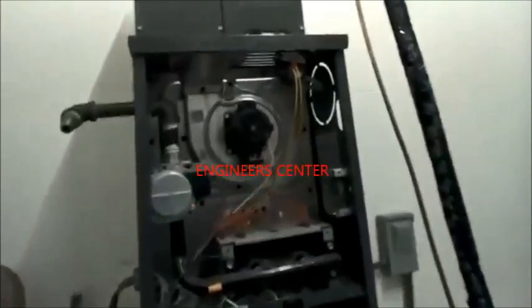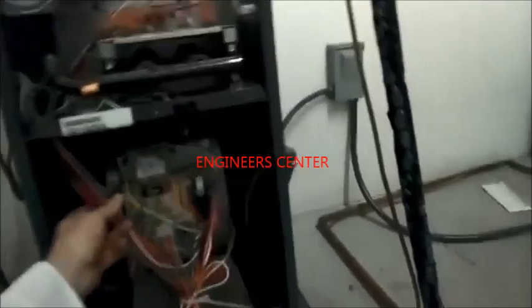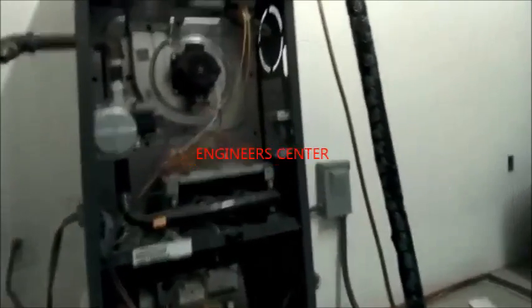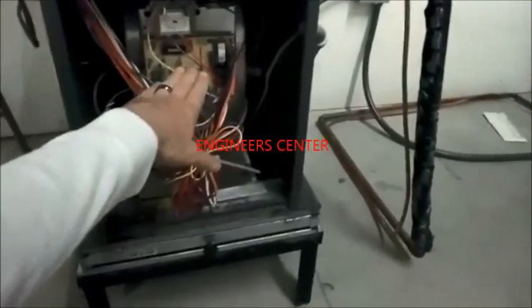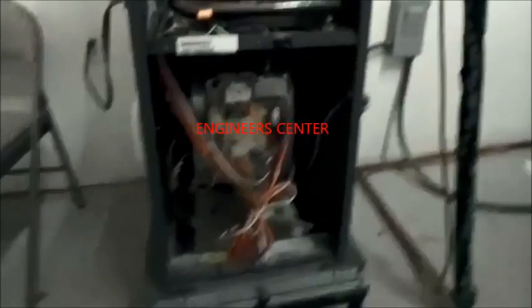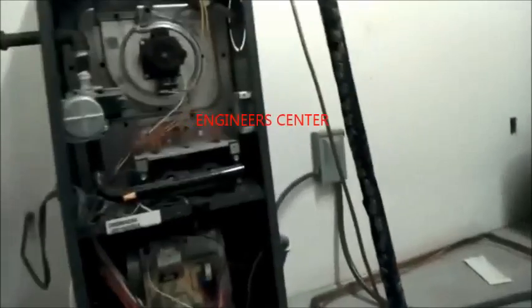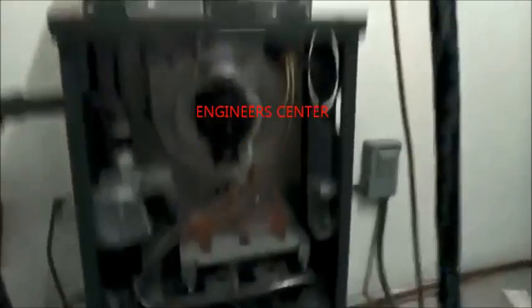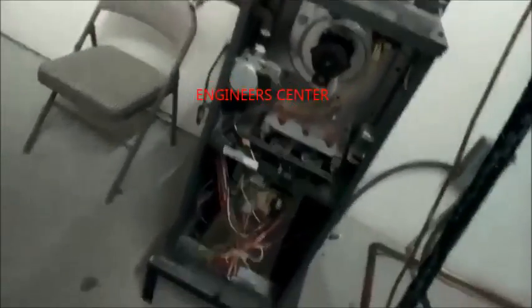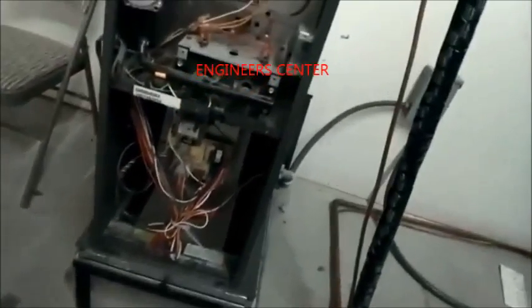Let's talk about heating real quick, because the electrical has to do with heating too. In heating, you really have a circuit board that's generally doing everything for you. This is where knowing the sequence of operation really comes in, because on most furnaces, let's say this thing was broken and we wanted to fix it, we would simply turn the thermostat on to heat, auto, 90 so it would stay on, and we'd sit here and we'd watch it.